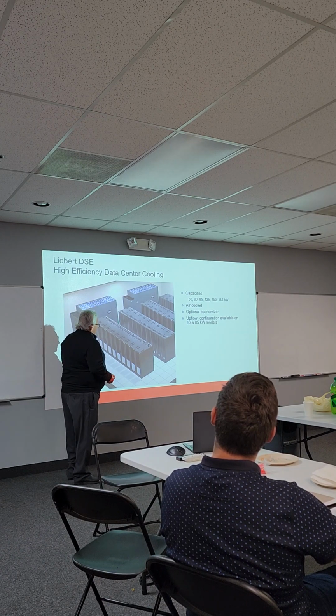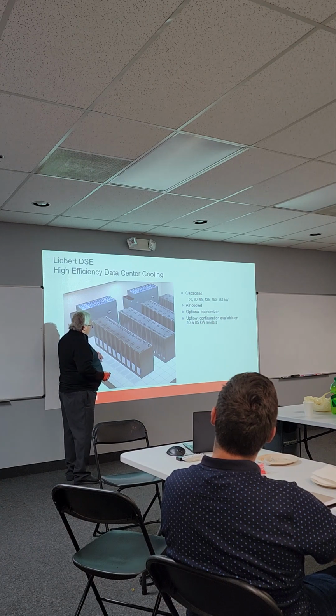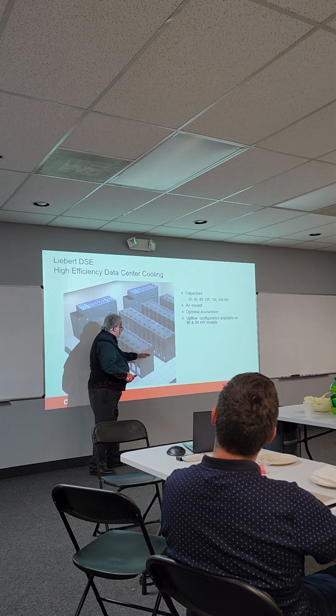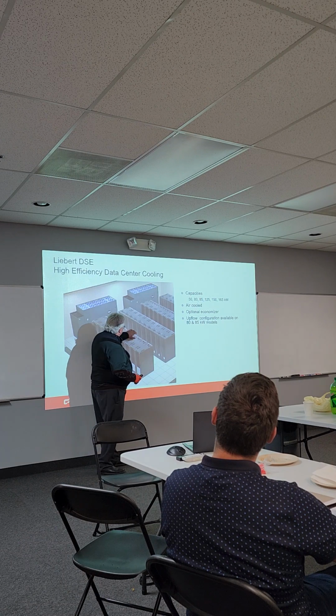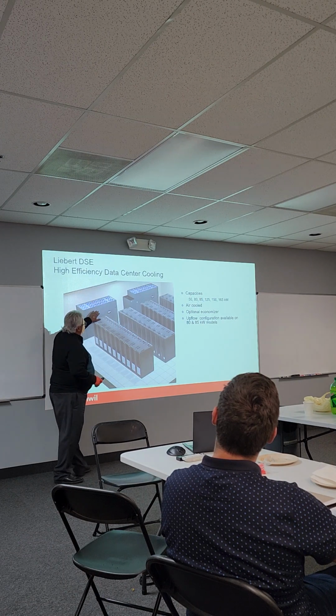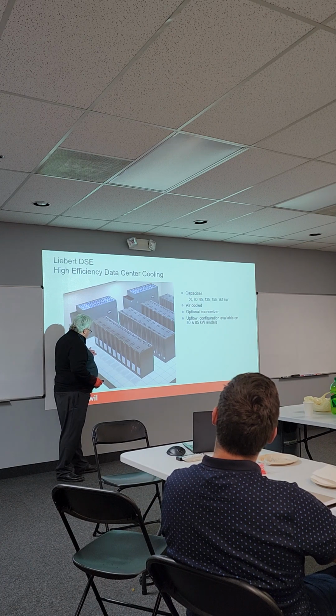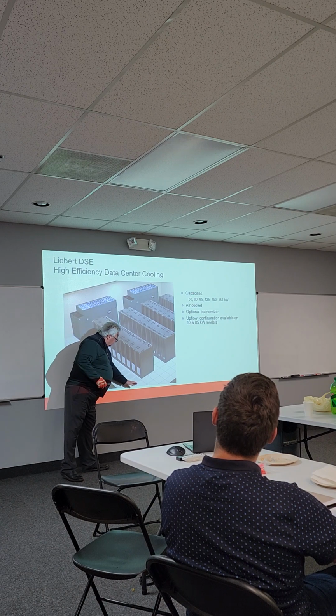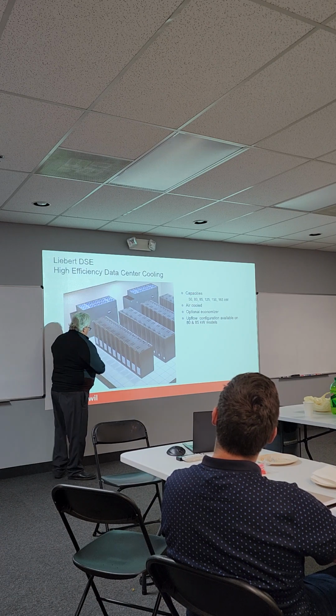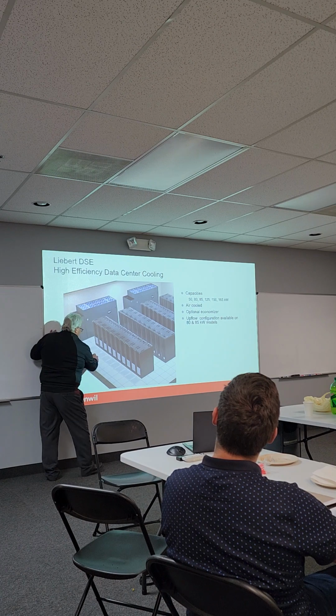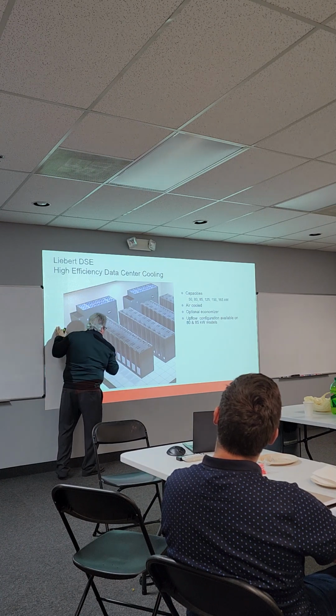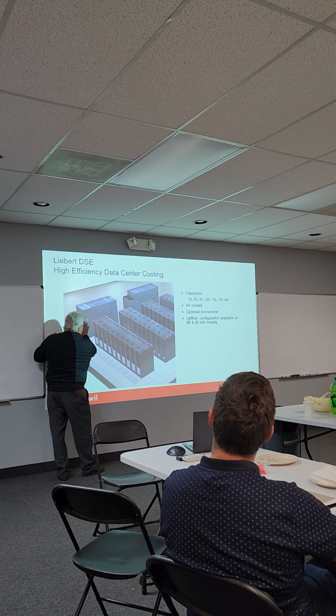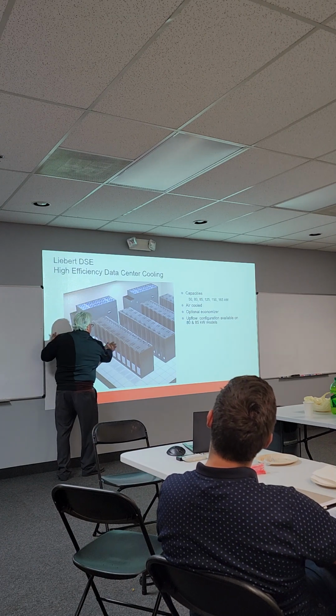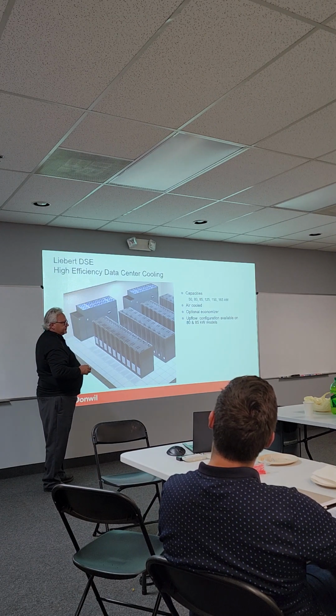So I got off the beaten path a little bit there, but kind of remember that, cold aisle, hot aisle. This isn't bad. What you want is that hot air right in the middle to come back to the unit. And what if I put containment here? What if I enclosed this and kept the cold air so it couldn't go anywhere else but through the servers? You think that'd be a good idea?